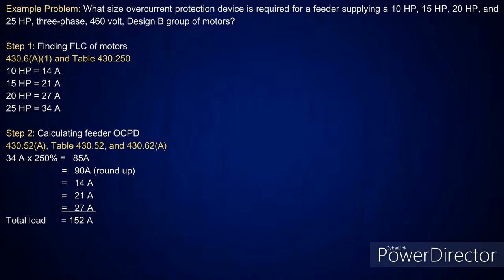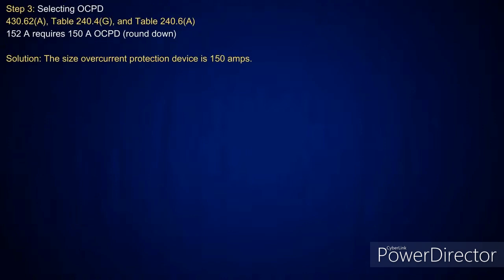So go look at table 430.52, pick up your inverse time circuit breaker. It says take it at 250%. I take that 34 amps at 250%, it's 85 amps. I'm going to round up to 90 amps, add the rest of the motors together, gives you 152 amps. And then you'll see here, then I drop down.